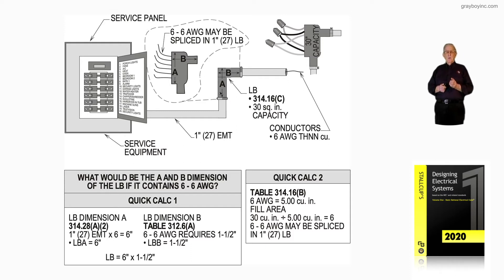Now, notice in calculation two, table 314.16B, six AWG size conductors would have a cubic inch rating of five. So, the fill area, 30 cubic inch area divided by five cubic inch would be six.